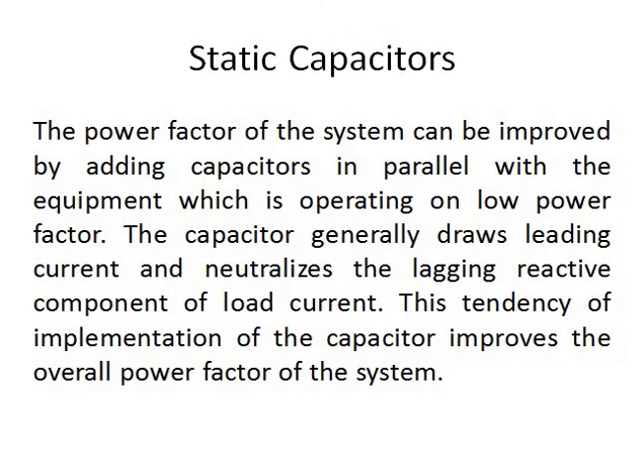Static capacitors. The power factor of the system can be improved by adding capacitors in parallel with the equipment which is operating on low power factor. It may be a capacitor or it also may be a capacitor bank. The capacitor generally draws leading current and neutralizes the lagging reactive component of the load. This tendency of the capacitor improves the overall power factor of the system.